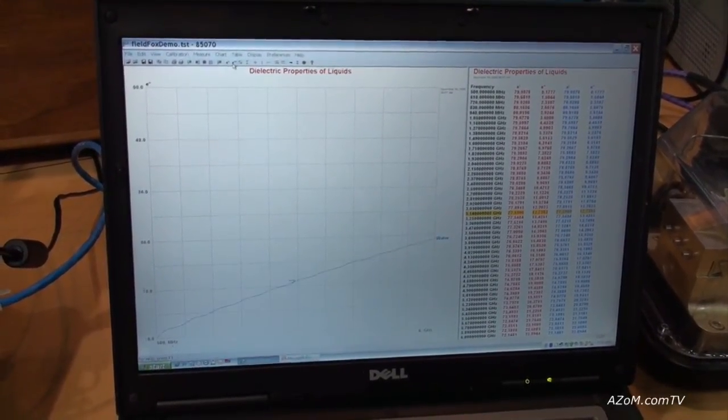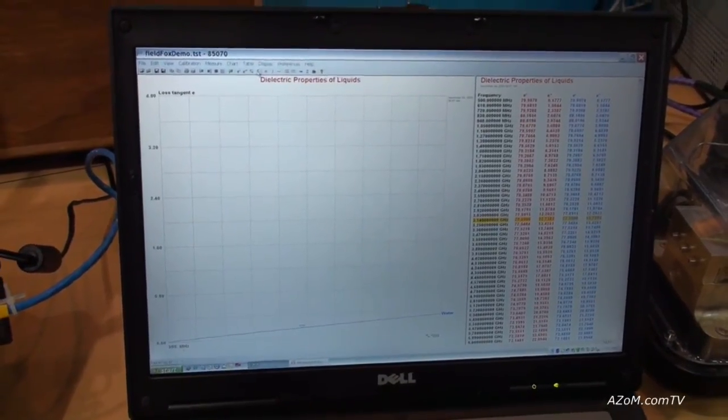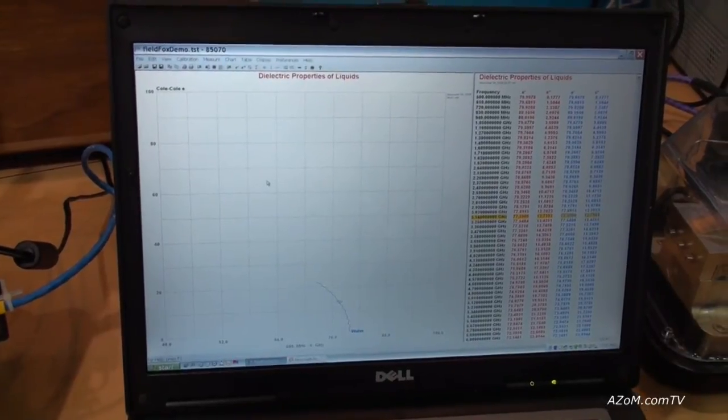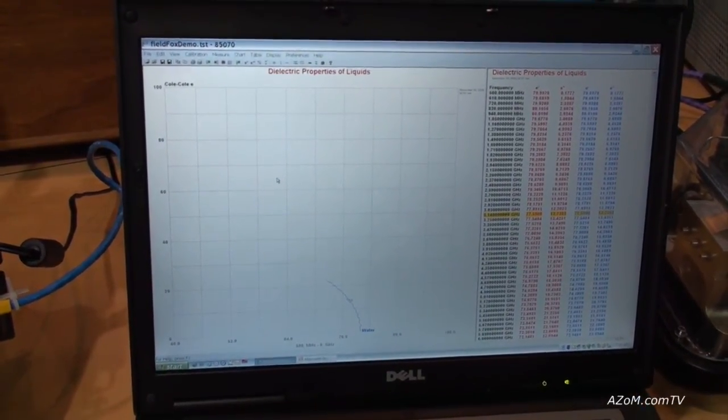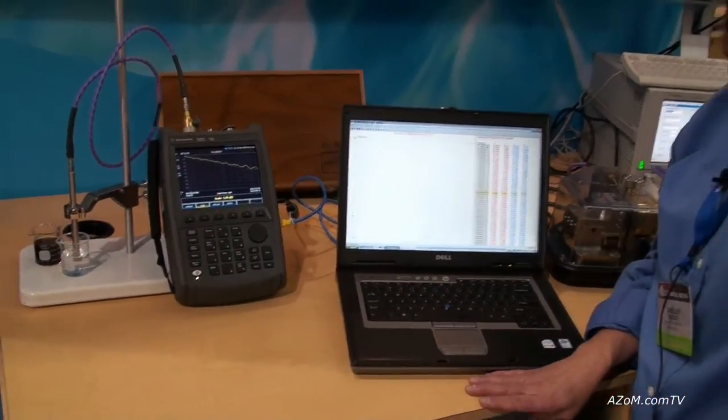And we can look at the imaginary part, loss tangent, and of specific interest to liquids is Cole Cole. This network analyzer goes up to 6 gigahertz. This setup works with all of our network analyzers. The probe will go up to 50 gigahertz with a PNA network analyzer.